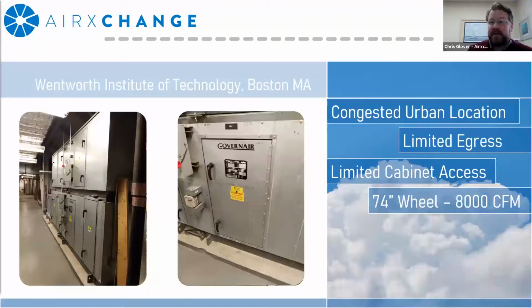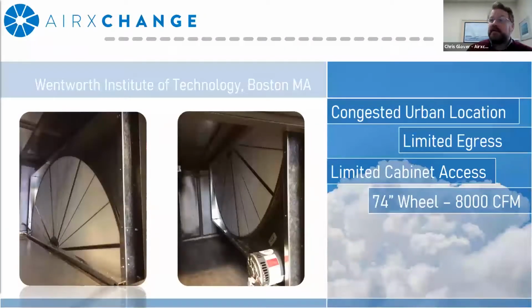This device was an 8,000 CFM wheel, and we provided the kit form for this building. So all the pieces were able to be taken off the truck, brought up through the elevator, and through the access, and we were able to get it into the cabinet without any structural or unit modification. That's kind of what the feature was for this design. And everything got built up inside the air handler.